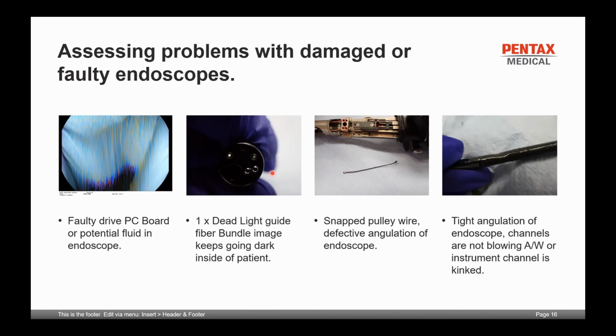Because during a colonoscopy, a colon is full of folds. So if the good light goes up against the fold of the colon and the bad light, the light guide that has not got any light, is meant to be shining out and it doesn't, it casts a very bad shadow, and sometimes to the extent that they cannot see. During a gastroscopy, when the doctor does a retroflex maneuver to look back up at the opening of the stomach, due to the fact that there's only one light and they're so far away from the visualization, the image looks completely dark. So if at any stage you get a doctor or an endoscopist stating that the image is dark, have a look at the light guides.